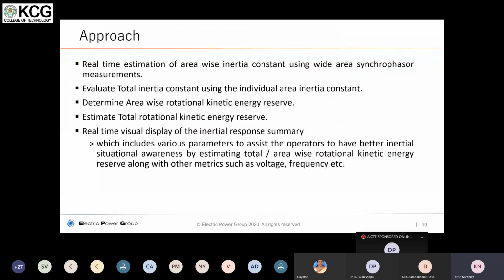And the approach, actually what we have done is, we will take the real-time area-wise inertia constant using wide area synchrophasor measurements. That means essentially we have to divide the bigger synchronous grid into several areas. When you divide them into several areas, you place the PMUs in those areas which are of interest to you, and then you measure the disturbances and evaluate the inertia constants based on the dynamic equations. There are several methods which I will discuss. Two of the most important methods are one that utilizes a disturbance-based methodology and another that uses ambient data. That means the normal synchrophasor data itself can be used in real time to evaluate real-time inertia, based on the sampling of the synchrophasors.